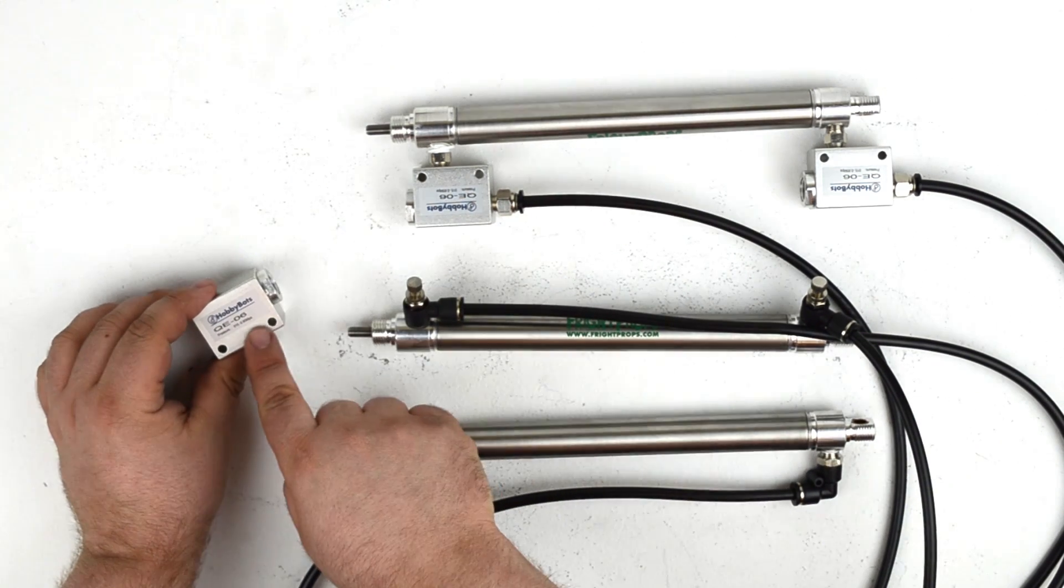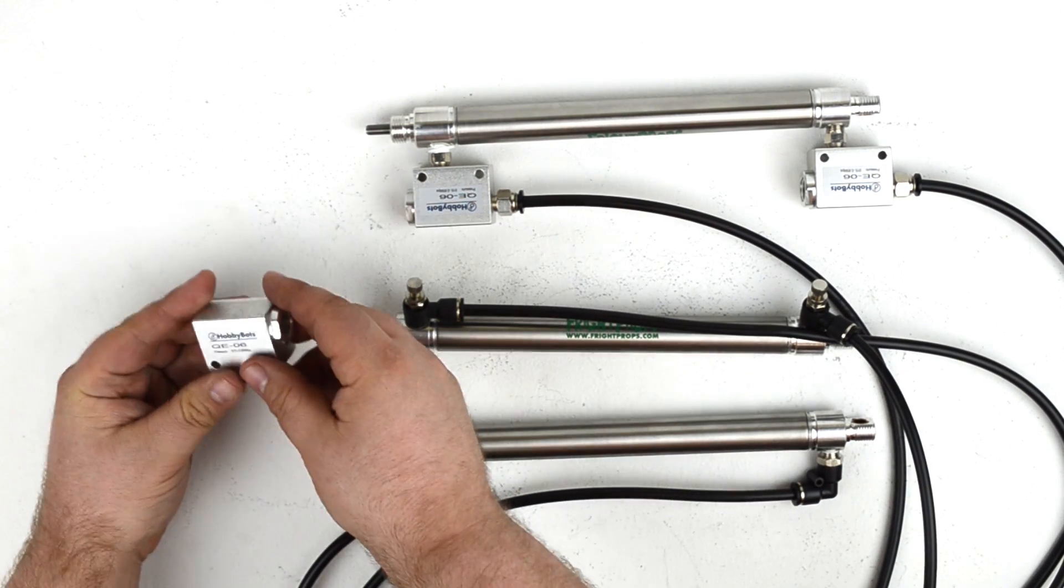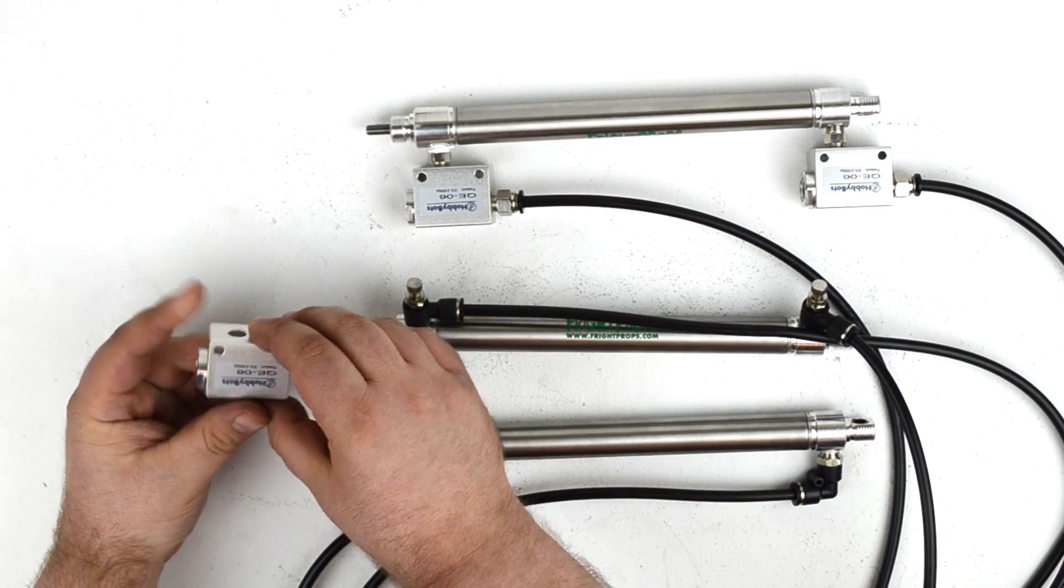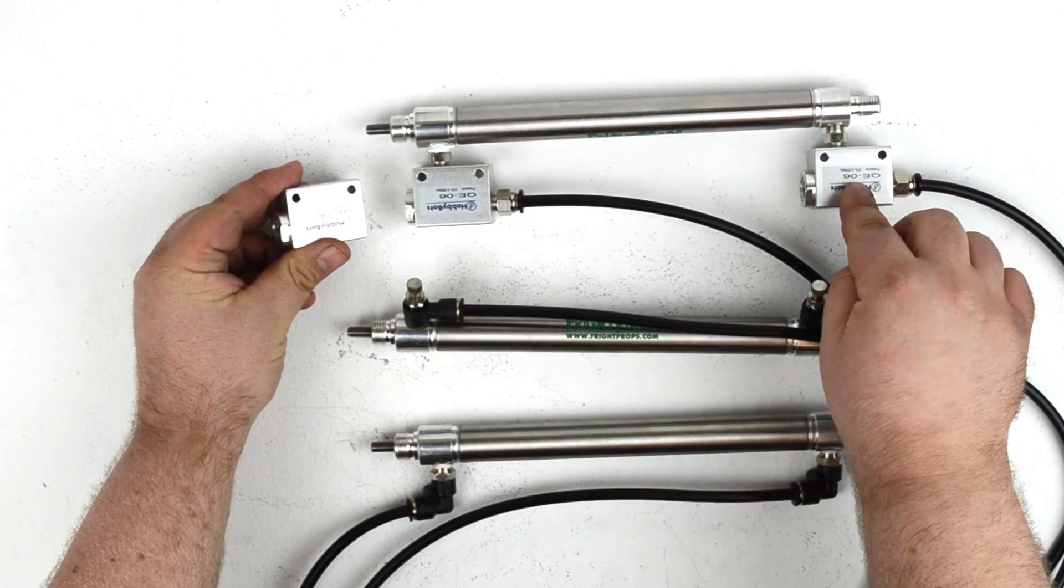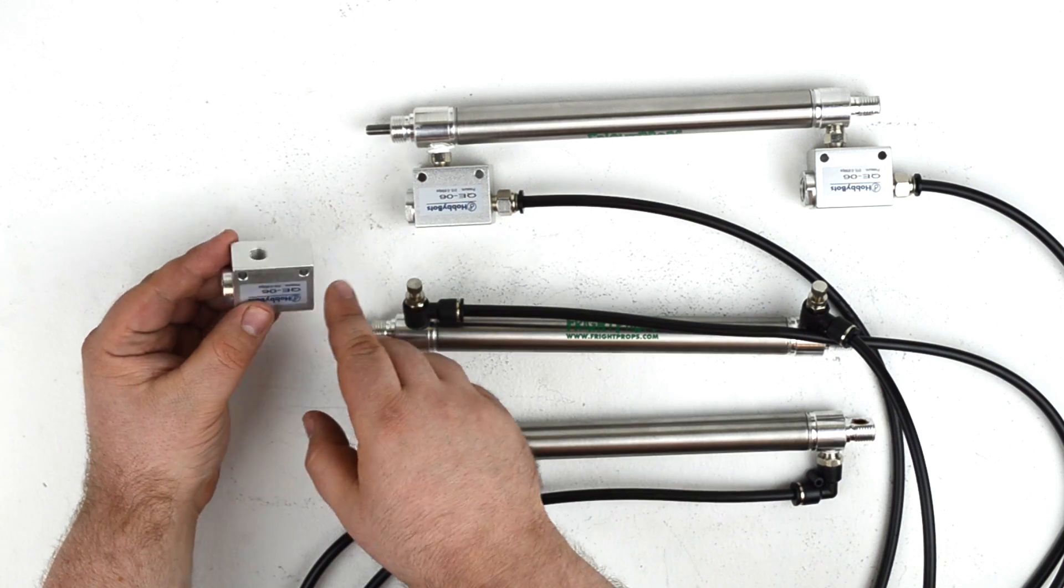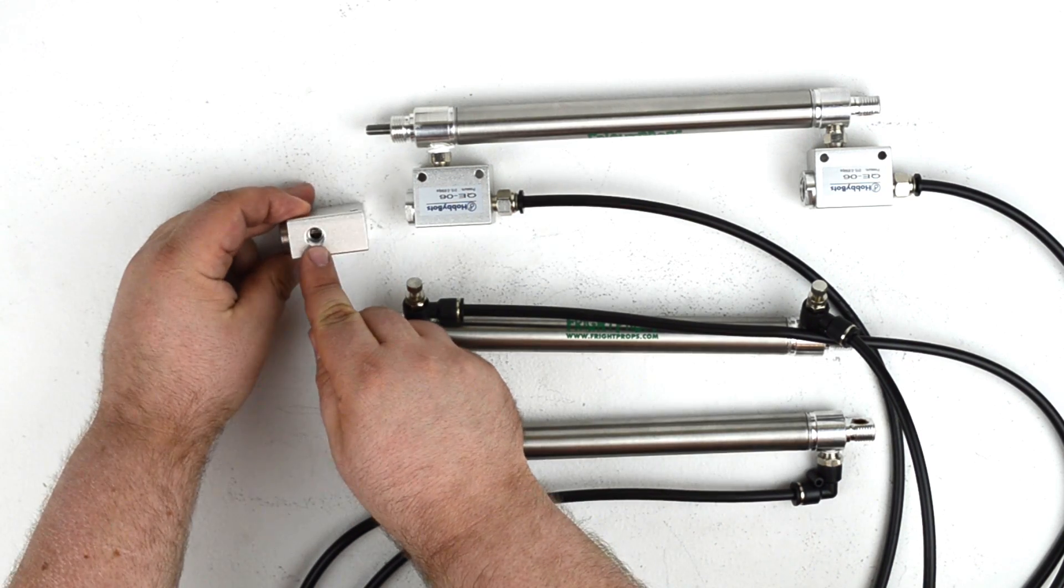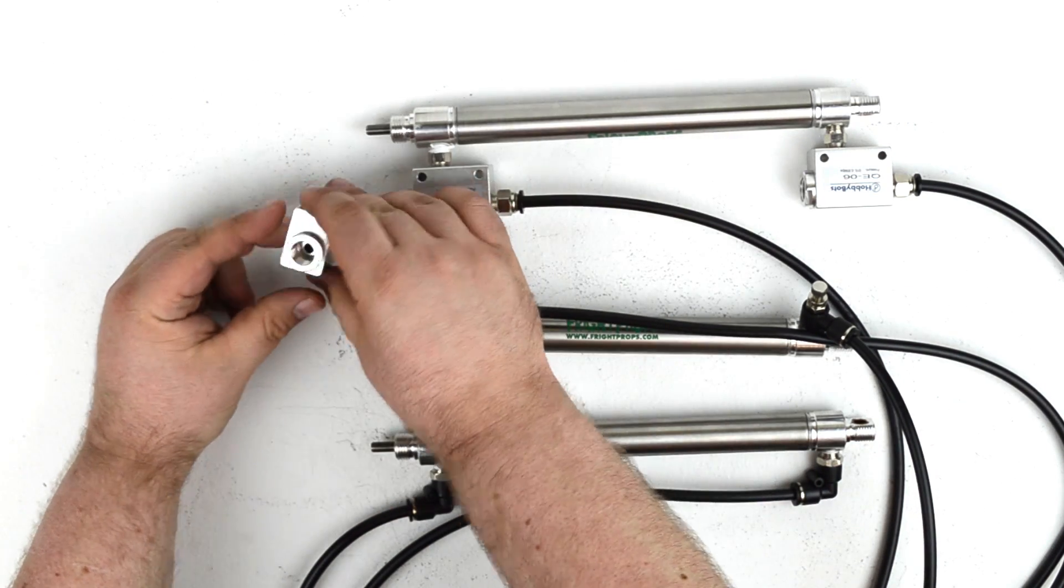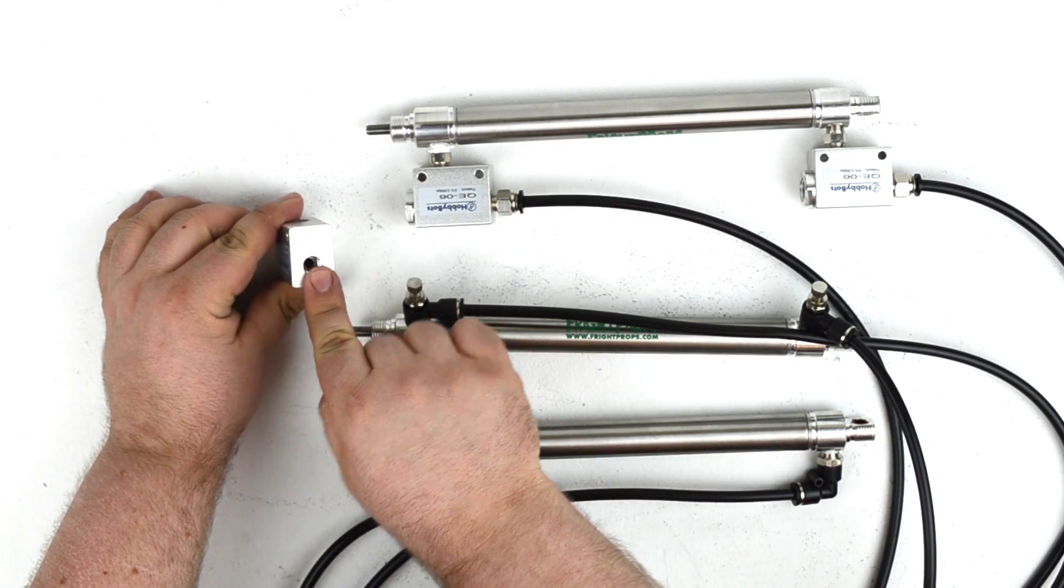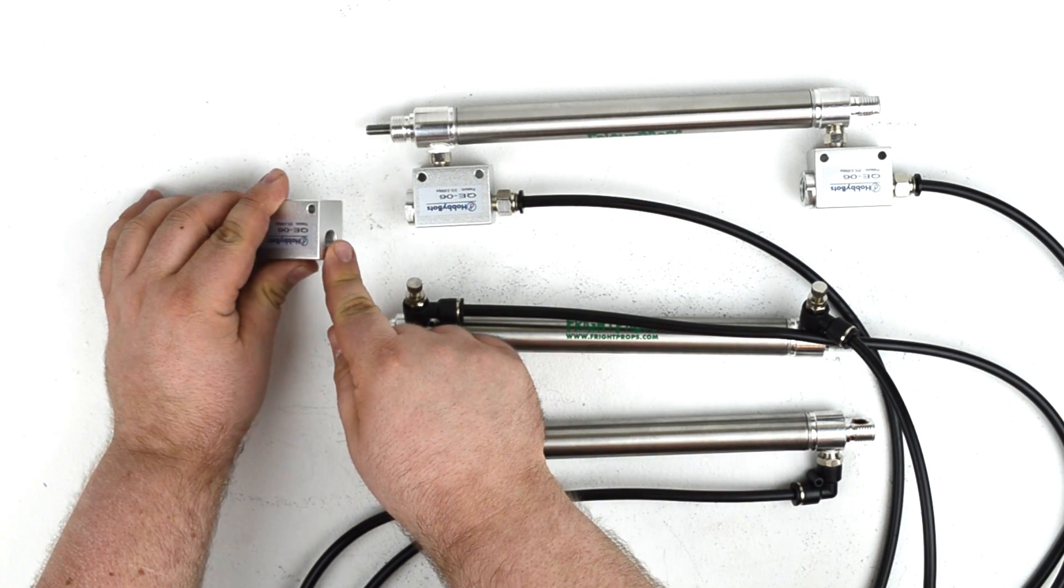Well that's where something called a quick exhaust valve comes into play. A quick exhaust valve is essentially a valve that attaches to the cylinder ports. This is one detached here. It has three ports of its own. So it has one port that connects to the cylinder, another exhaust port, and then the third port where the air goes into the cylinder.